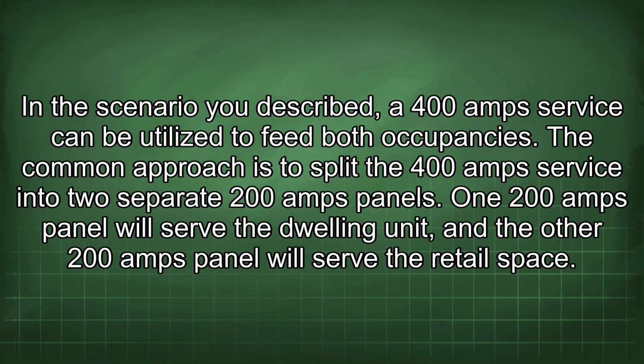In the scenario you described, a 400 amp service can be utilized to feed both occupancies. The common approach is to split the 400 amp service into two separate 200 amp panels. One 200 amp panel will serve the dwelling unit, and the other 200 amp panel will serve the retail space.